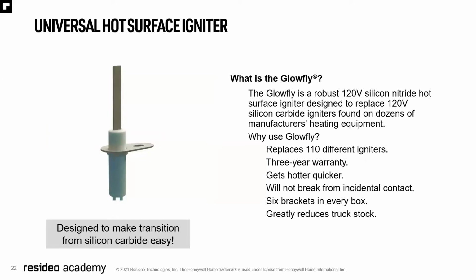Universal hot surface igniter. We came out with the Glowfly. It's a robust 120-volt silicon nitride hot surface igniter designed to replace the 120-volt silicon carbide igniters found on dozens of manufacturers' heating equipment. So I use Glowfly. It replaces 110 different igniters. It has a 3-year warranty.